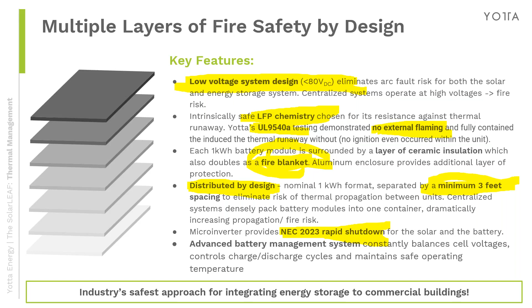As I said, UL 9540, 9540A, UL 1973, and 1741 SA and SB. California has its own requirements too, so we're also required to be on the CEC listing for both the inverter and the battery, JA12 listed, and of course Rule 21 or NEC 690.12 rapid shutdown requirements.